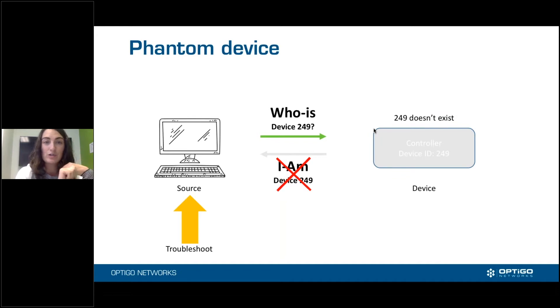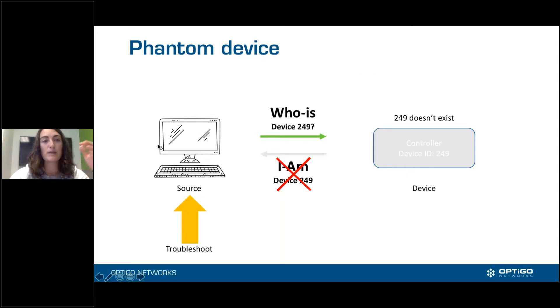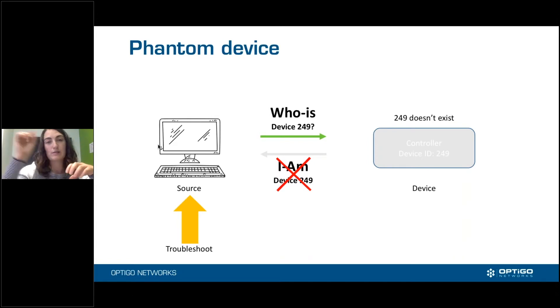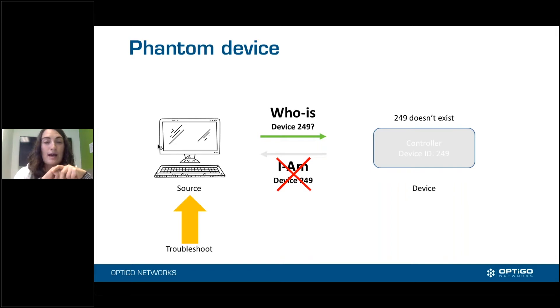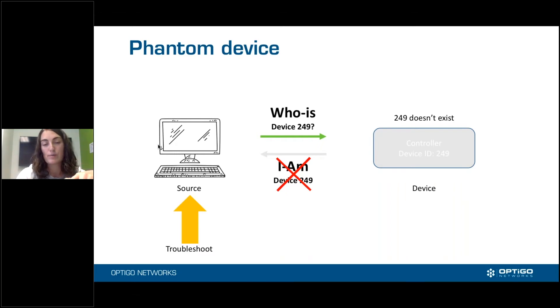Don't spend all your time looking for device 249 and figuring out why it's not responding, because the problem is actually that the source is programmed or is thinking for some reason that it needs to find device 249. From a troubleshooting perspective, ask: is it configured to look for device 249? Or is it receiving a packet from someone else that it's supposed to route to device 249? It could be a controller or router that's asking Who-Is 249 on behalf of another device, meaning a different device further down may be the real problem.